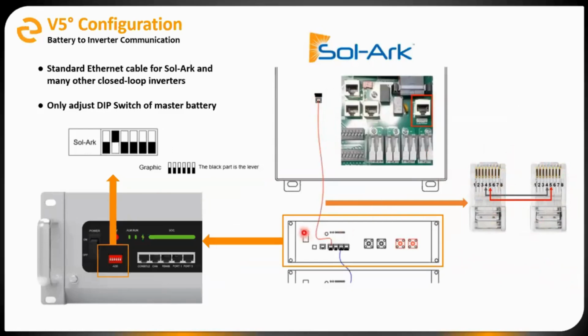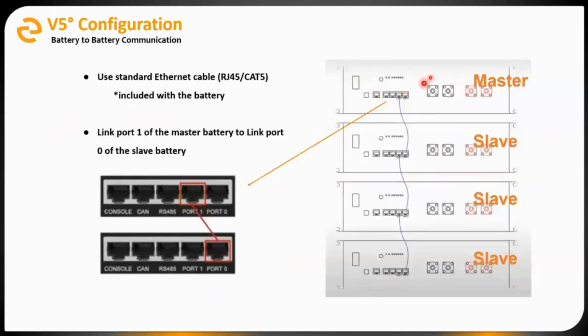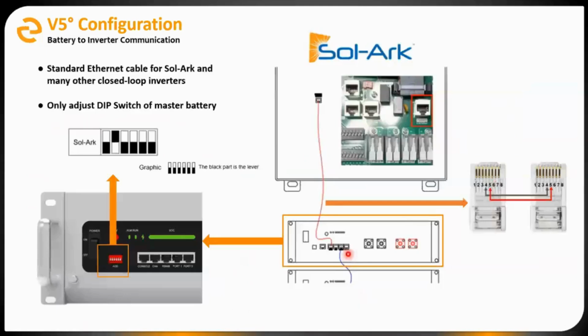The other thing to look at in this step is the battery dip switches. These little switches on the front of the battery can be adjusted to tell the battery what inverter it's using, so it knows how to talk with it correctly. We only have to adjust the dip switches of the master battery. Just this very top battery that's communicating with the inverter, you adjust the dip switches on it, and the switches on all the other batteries in the system, you just leave those off.